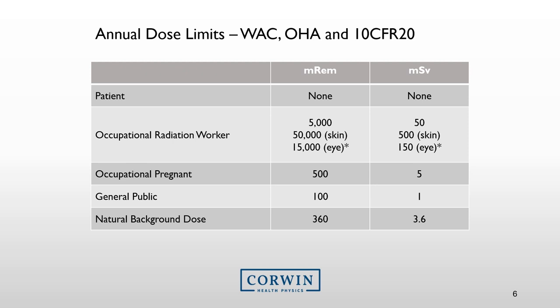If you are occupationally pregnant and have declared your pregnancy, the maximum dose you can receive is 500 millirem, typically limited to 50 millirem per month during the pregnancy. The general public — individuals who are not radiation workers — is limited to 100 millirem per year. To put this in context, the natural background radiation exposure in the United States is about 360 millirem per year, and most occupational radiation workers receive less than 360 millirem while working at their medical facility.